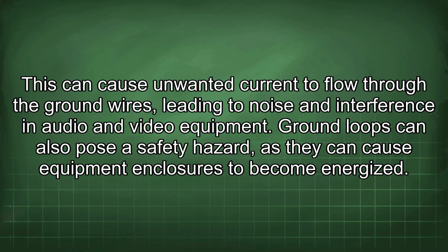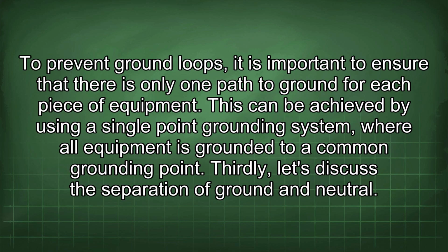equipment. Ground loops can also pose a safety hazard, as they can cause equipment enclosures to become energized. To prevent ground loops, it is important to ensure that there is only one path to ground for each piece of equipment. This can be achieved by using a single-point grounding system where all equipment is grounded to a common grounding point. Thirdly, let's discuss the separation of ground and neutral.